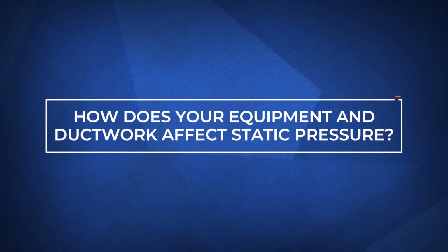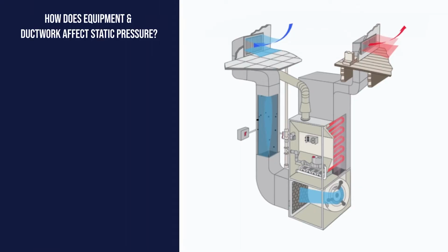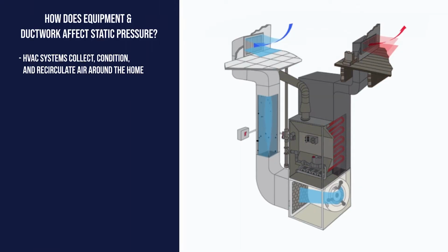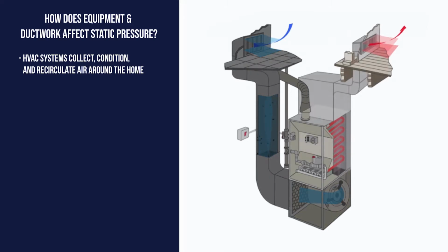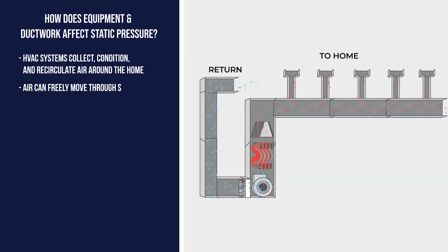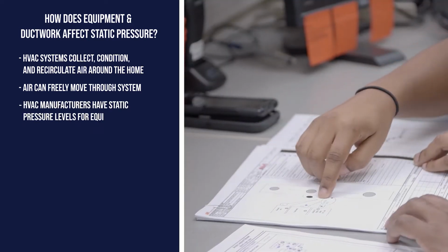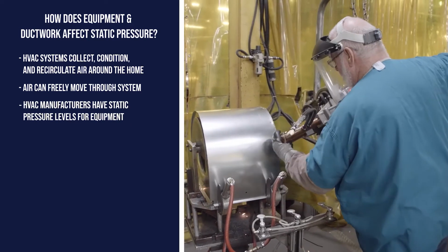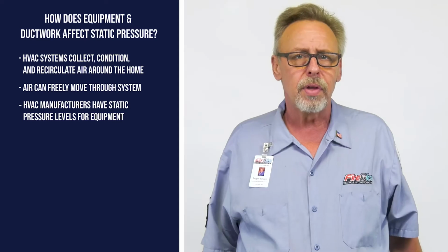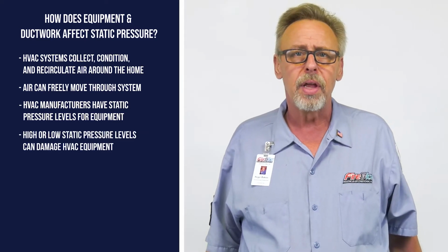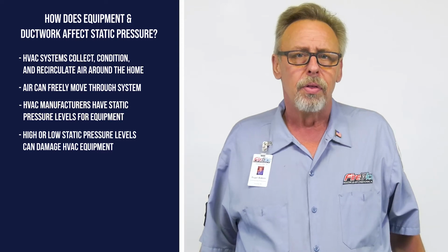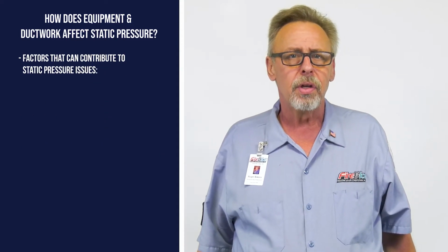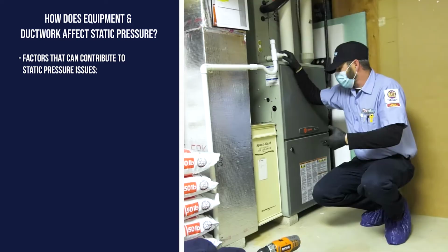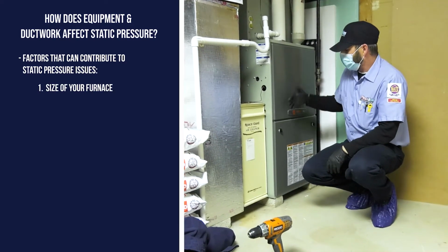How does your equipment and ductwork affect static pressure? In an HVAC system, air is collected from the home by a blower motor inside your furnace, conditioned and then recirculated throughout the house. When your HVAC system is dialed in, air is able to move freely throughout the ductwork and into your home with optimal static pressure levels. HVAC manufacturers have a preferred range for static pressure levels within their equipment. When static pressure levels fall above or below that range, damage can occur to your HVAC equipment. There are a number of contributing factors that can cause increased static pressure, such as the size of your furnace. First, the size of your furnace has a lot to do with static pressure levels in your home.